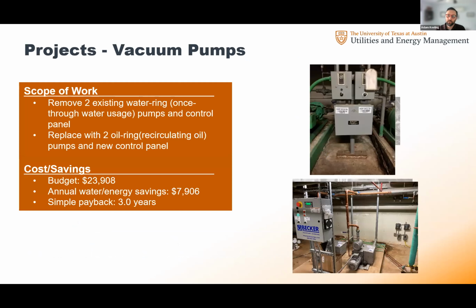Another example is vacuum pumps, more of a water project. Vacuum pumps are used a lot in labs. This specific project has actually been done three different times, using what's called water ring pumps. They have once-through water going through the pump constantly, running 24/7, using the water to cool the pump, then dumping the once-through water to the drain. There are other types using recirculating oil instead of once-through water. So again, easy, low-hanging fruit, saving $8,000 in water every year.